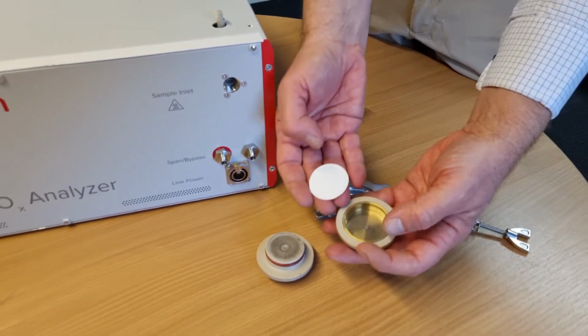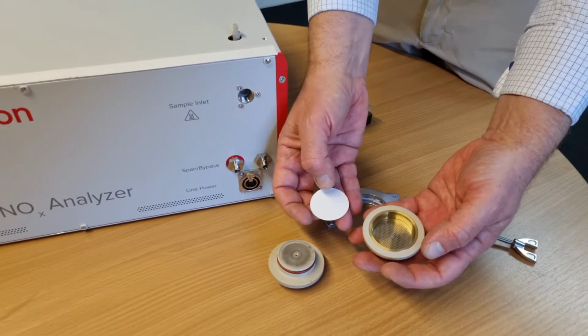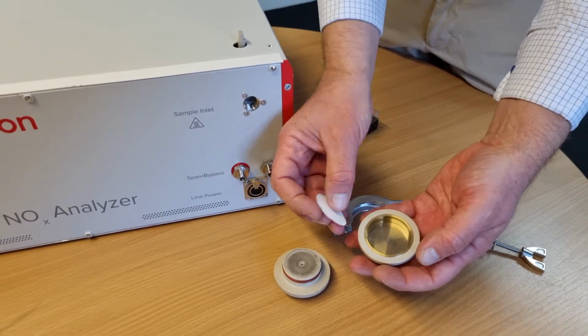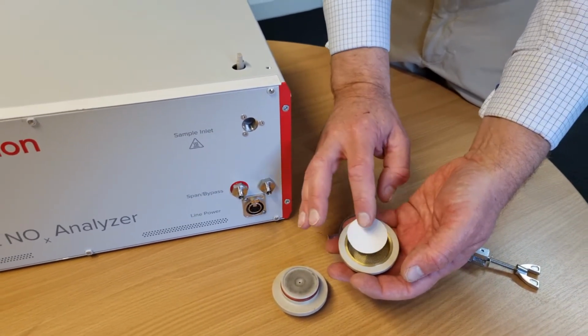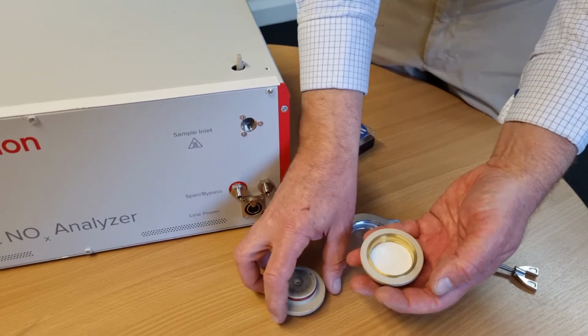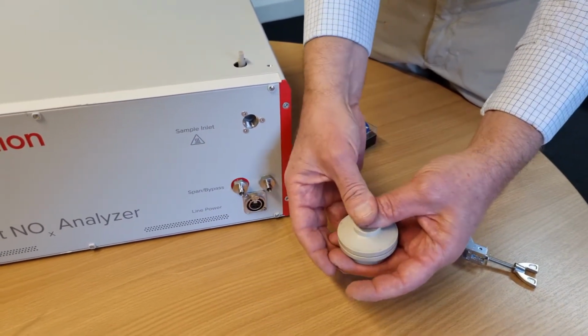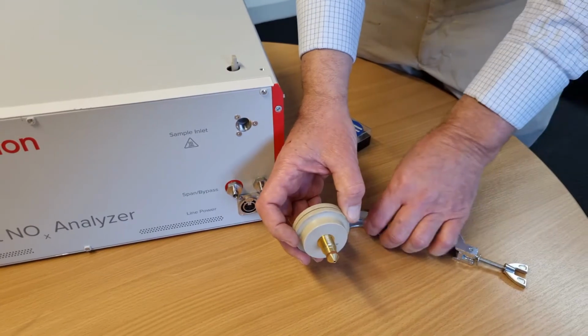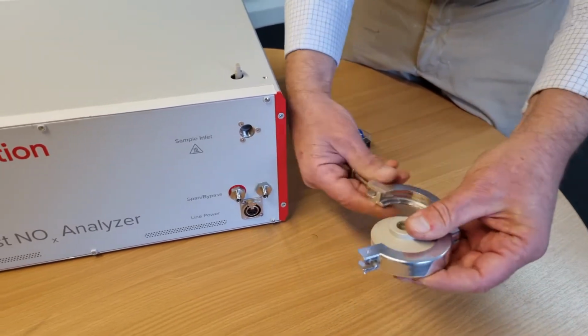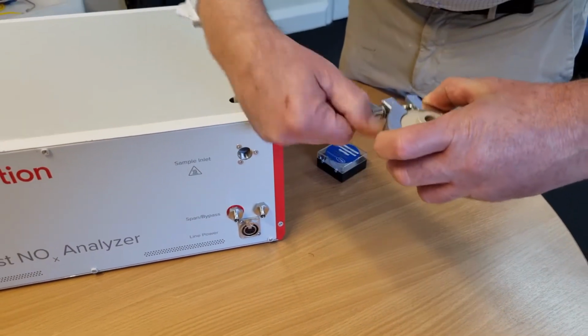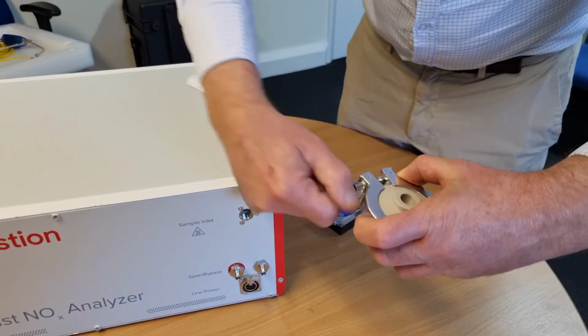So the gauze goes in first. There are two sides to the sample filter. There's a woven side and a fluffy side, and it's the fluffy side that goes up, and then the two halves get pushed together and the clamp goes back over, and then that can be screwed into the front of the analyzer.